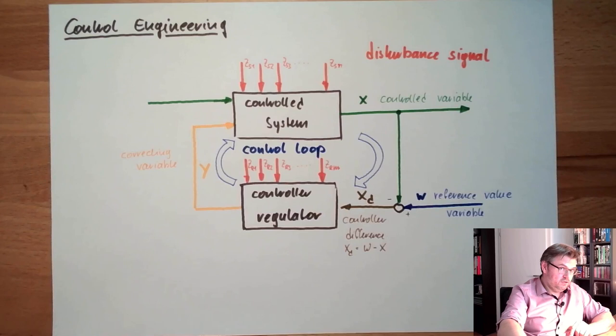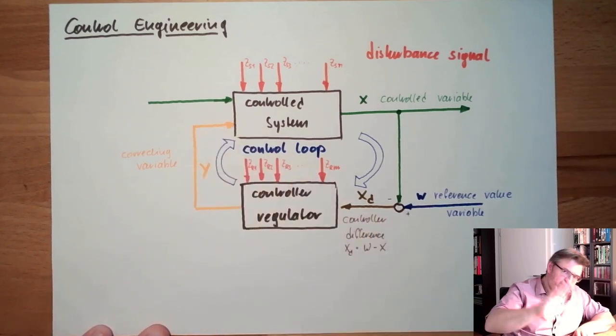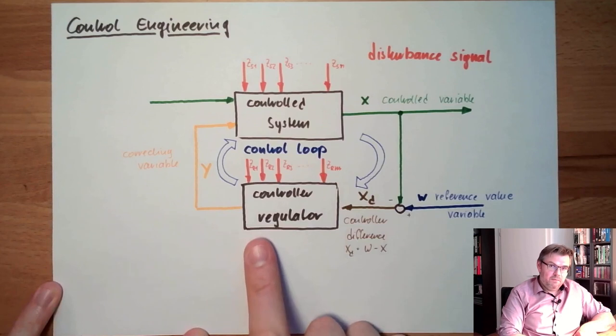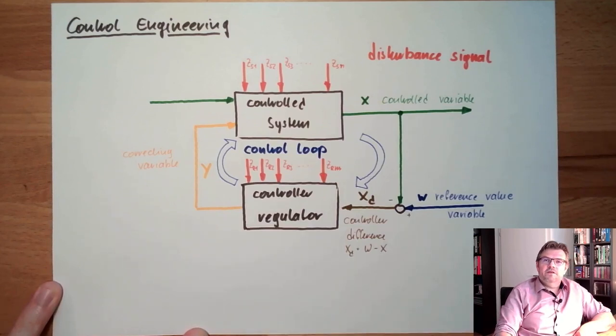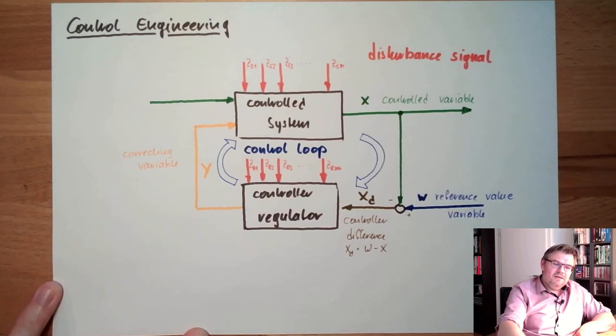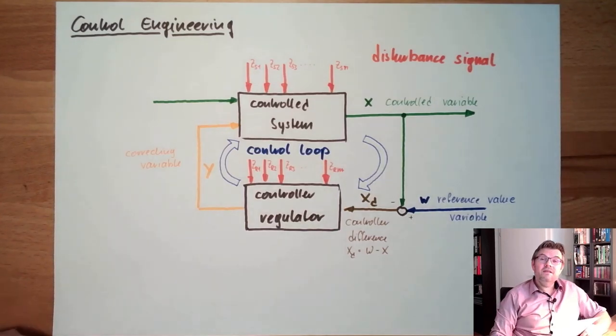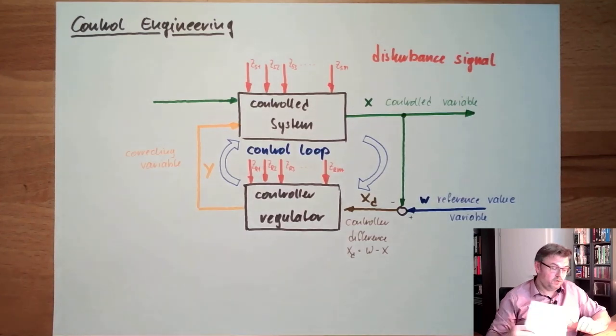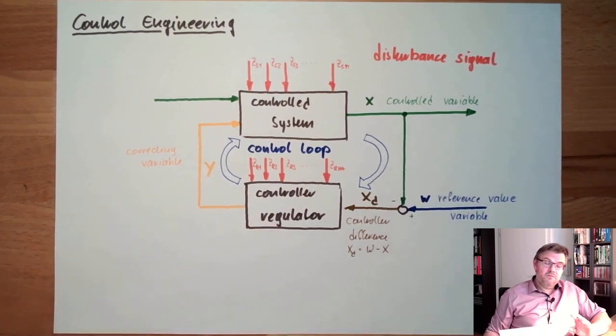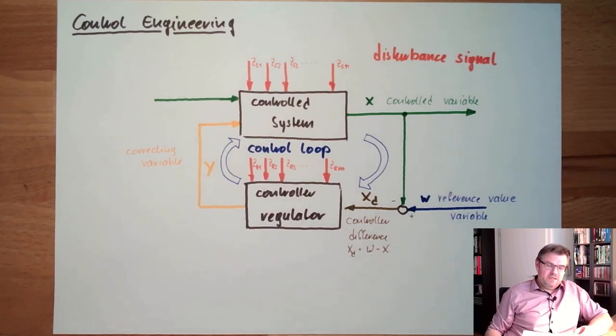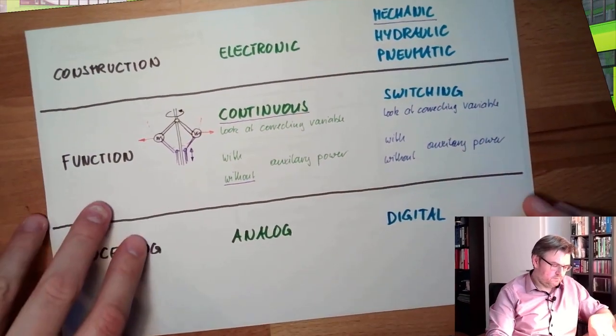Analog controllers do not have this issue — if the input changes, the output changes immediately. Digital controllers need a little bit of time. However, with nowadays' calculation power, even in the tiniest parts, this disadvantage is usually not that big anymore. But sometimes you may run into this issue if you're not taking care about cycle times in some PLCs working as controllers — you might get instability simply because you're processing too few snapshots of reality in your digital controller.